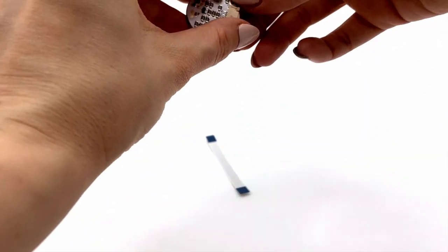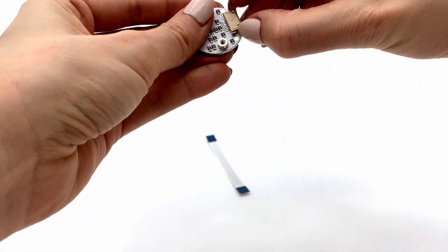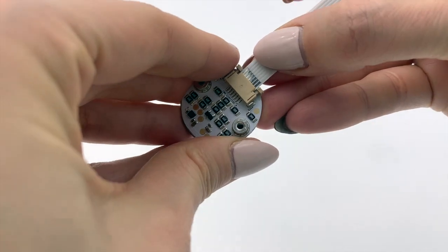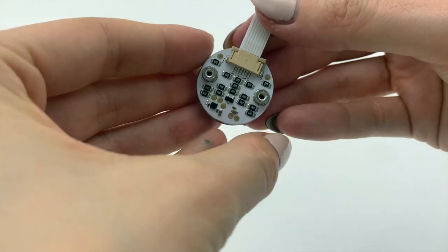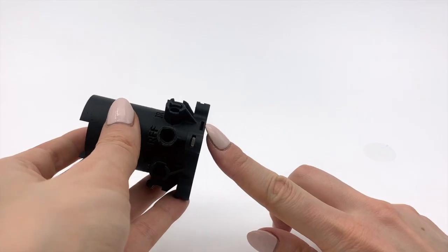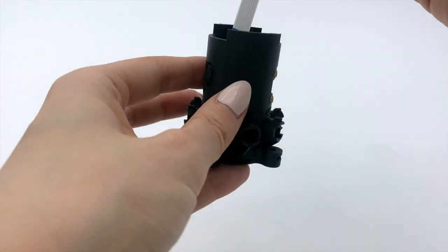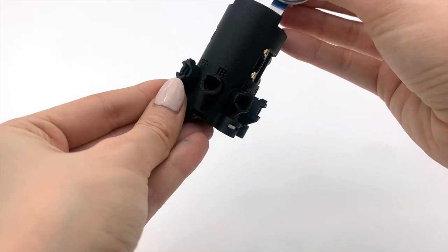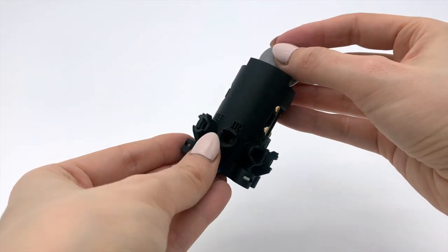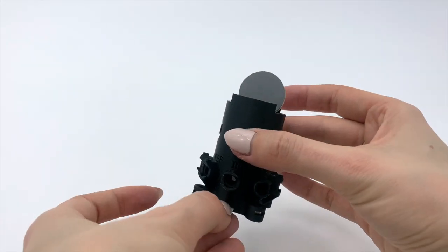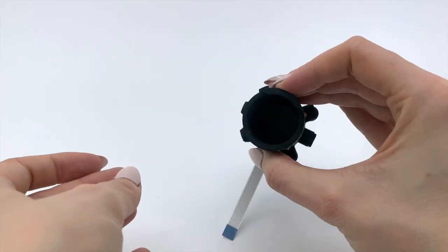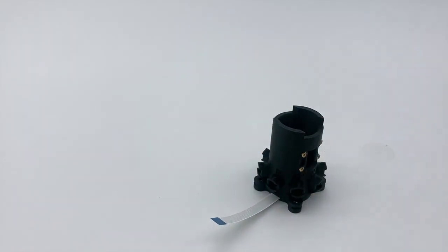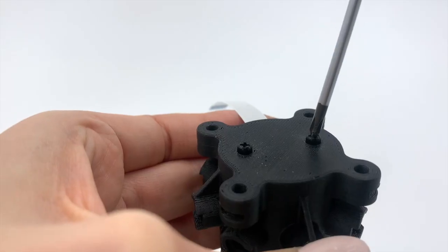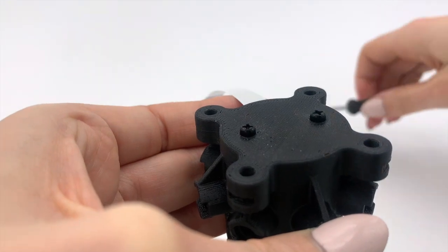On the cable connector, pull the beige colored tabs out to open it. Insert the cable into the cable connector, then push the tabs inward to secure. Take your vial holder and feed the cable through the small slot on the side. You want the blue part of the cable facing up. When you pull the cable through, you'll have the thermal pad facing up. Take two of your 4mm screws to secure the heating PCB to the vial.